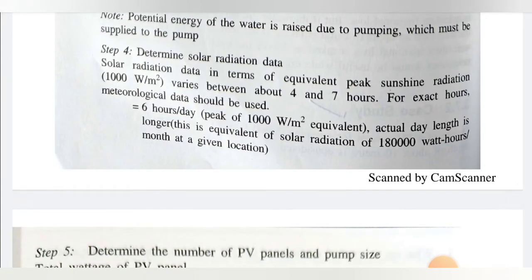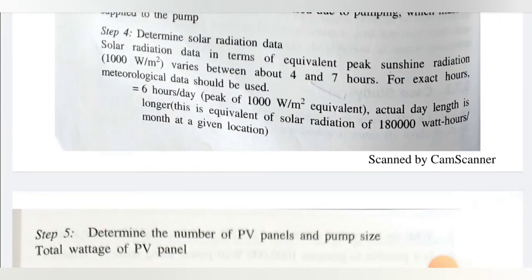Step 4: Determining solar radiation data. Solar radiation in terms of equivalent peak sunshine at 1000 W/m² varies between about 4 to 7 hours. For exact values, meteorological data should be used. Here we take 6 peak sunshine hours per day, equivalent to a solar radiation of 180,000 Watt-hours per month at a given location.